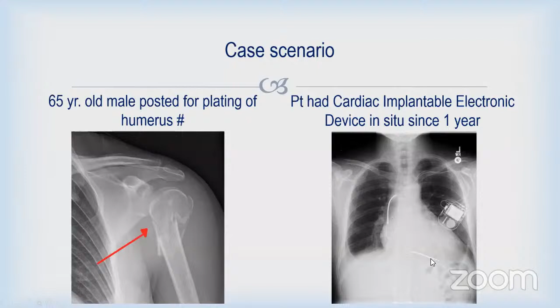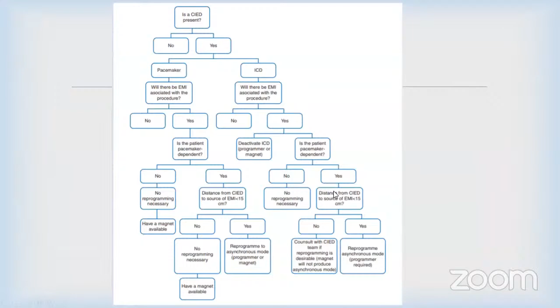Is the patient pacemaker dependent? What are the factors which will tell you he is pacemaker dependent? If all the activity is by the pacemaker, he has symptomatic bradycardia. If AV nodal ablation has been done, yes. If the distance is less than 15 centimeters, of course, yes. Then you need to reprogram with the reprogrammer, not with the magnet. In an ICD, if you use the magnet, it will only abolish anti-tachycardia, not the pacing. So to get an asynchronous mode plus AICD abolishment, you need a reprogrammer. If the distance is high and there is no EMI, the magnet just kept ready is enough, right?